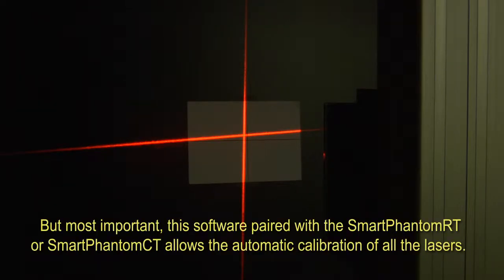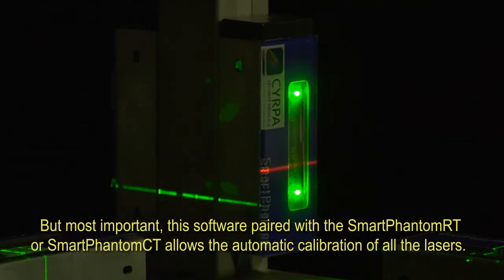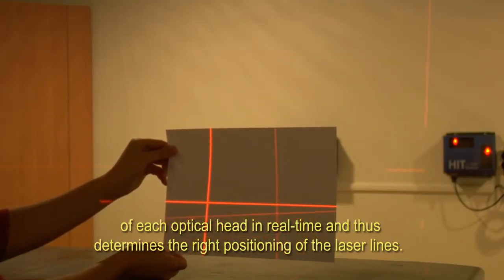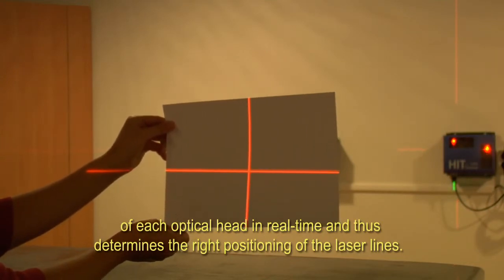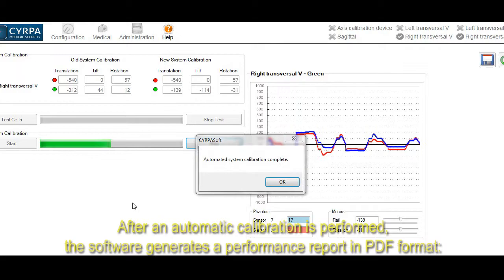Most importantly, this software, paired with the Smart Phantom RT or the Smart Phantom CT, allows the automatic calibration of all the lasers. When using the software for patient positioning, the software analyzes the position of each optical head in real time and determines the right positioning of the laser lines. After an automatic calibration is performed, the software generates a performance report in PDF format — a CYRPA quality certificate that testifies to the correct positioning of all laser lines.